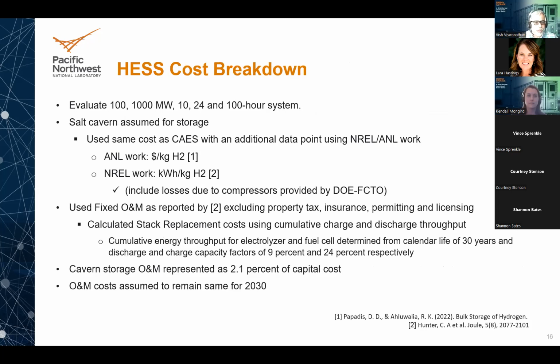The breakdown for hydrogen energy storage system, we evaluated for 100, 1000 megawatts, 10, 24, and 100 hours. Assume salt cavern for storage. We piggybacked on our findings from compressed air, but we also included one data point based on Argonne National Laboratory's work that determined the dollars per kilogram of hydrogen, and then NREL work that determined how many kilowatt hours is obtained in discharge from 1 kilogram of hydrogen. And Fuel Cell Technology Office has also provided us some losses related to compressors.